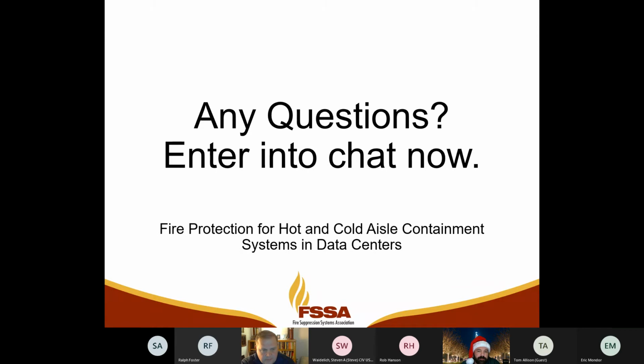My NFPA 75 committee is trying to gain back that control over UPS systems and data centers, which we've kind of lost to 855, and they're more focused on the energy storage applications and not the UPS applications. So we've got these big rooms in data centers. We all know that there's fire protection problems with lithium ion batteries, and they're just coming in and doing this, and they're not addressing fire protection. And I'm not even totally sure what the fire protection requirement should be yet in data centers for lithium ion installations. But I'll tell you what, it's got to be something.